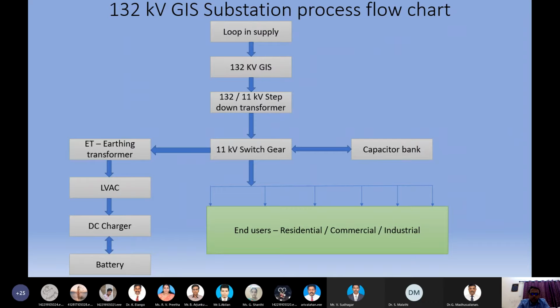And the capacitor bank has its own role in the power factor, to stabilize the 11 kV power supply, whether to eliminate or to add on to the power factor, like the rating for UAE is 0.99, which we are going to see in the coming slides, to maintain the power supply and avoid any kind of fluctuations. And the earthing transformer is a feeder for the LVAC room, which gives the power supply for the utilities in the power station, which are the small powers: CCTV cameras, AC supplies, access doors, and even the pump rooms. So the earthing transformer is completely the power supply for the substation, and the 11 kV switchgear is the supply for the complete end users.